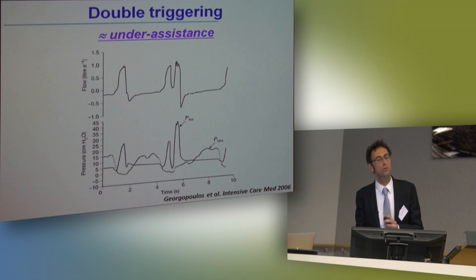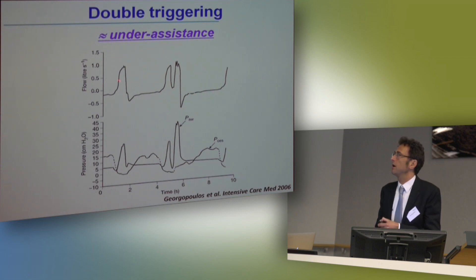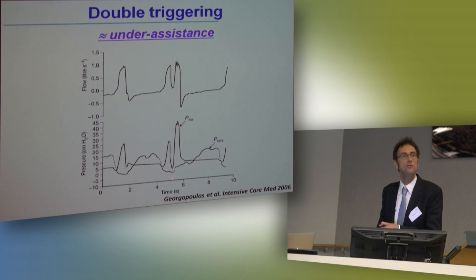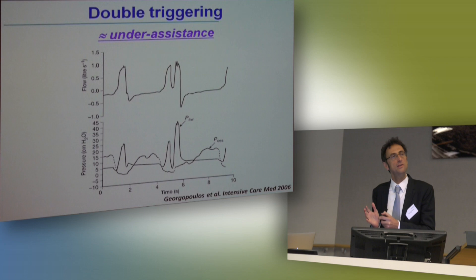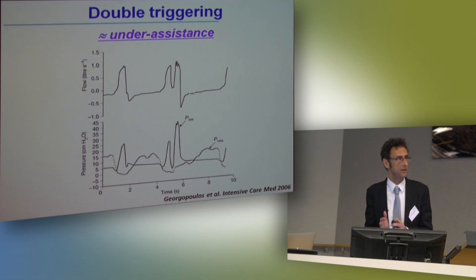What causes double triggering? Double triggering is caused by under-assistance. Looking at the flow, pressure, and esophageal pressure traces, double triggering is caused by a very intense inspiratory effort — so intense that the patient is able to trigger the ventilator twice with only one inspiratory effort. This means the patient is not receiving enough assistance.